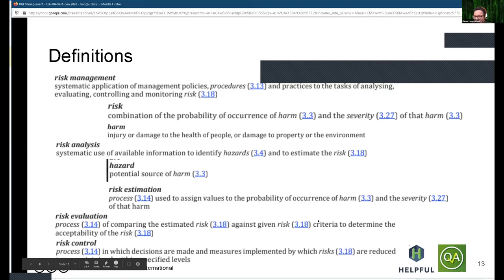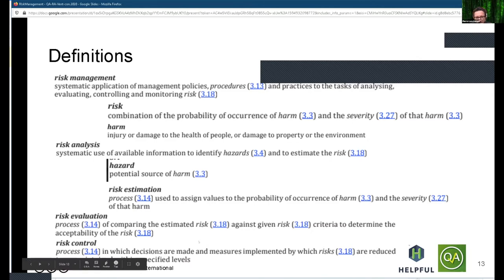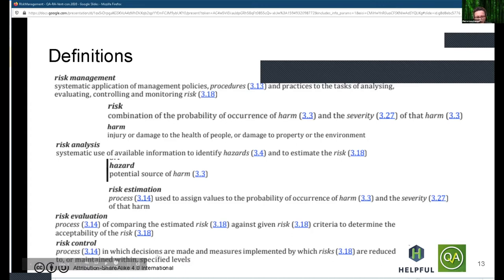Evaluation is the comparison of this estimated risk against a given risk criteria, and this comparison lets you decide whether the risk is acceptable or not. Risk control refers to decisions that are made and implemented to reduce the risk within a specified — meaning acceptable — level.